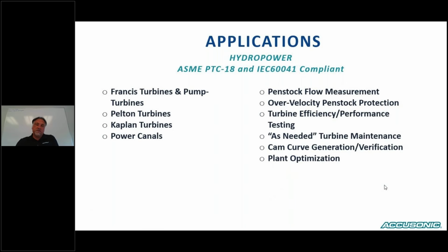You can do over velocity penstock protection, where you have the flow meter installed up near the intake of the unit, and you can trip an alarm that can close a gate if you get over a certain flow rate. You can use this flow measurement for turbine efficiency and performance testing. So the important thing there to note is that this technology is an absolute flow measurement technology. It's not a relative flow measurement technology. So it can be used to determine actual turbine efficiency and can be used for contractual performance testing.